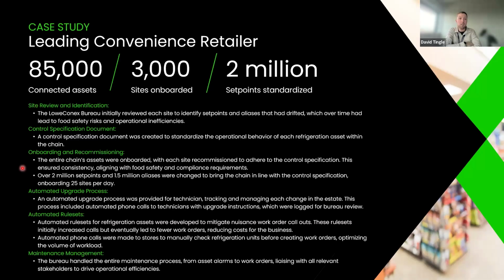For our bureau and software, we went through and reviewed every single setting, every single alias, and the entire configuration in line with building that spec. When we took it on they had lots of different manufacturers and types of kit, so we built the specification out alongside them and aligned everything to it through the bureau service and software. That equated to around 2 million set points we had to put back in line with manufacturer set points - it gives you an idea of how quickly an estate can drift from its design conditions from a set point perspective.